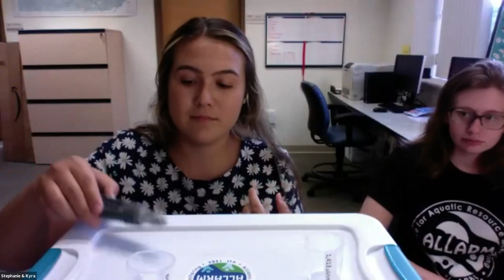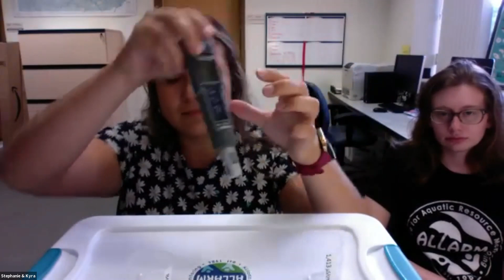Hopefully your values have stabilized. So again, you're going to press and hold that cal button for approximately 2 seconds. The second you see cal appear on the bottom of the screen and 84 begins to flash, release the button, and this calibration happens really quickly. So hopefully you're seeing an SA and an end, letting us know that you have successfully calibrated at the low range.